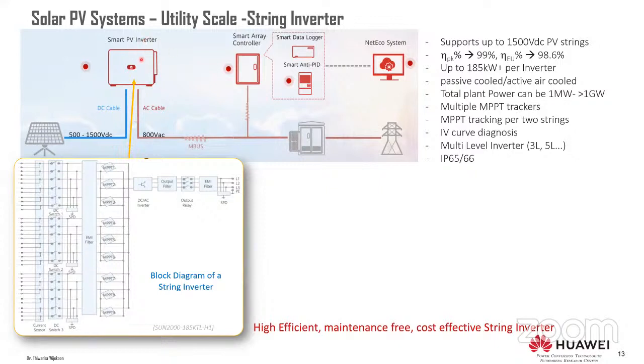The output of a typical inverter goes up to 800 volts AC, again very close to the AC limit, which is 1000 volts AC, and then you feed into the grid. Typical inverter efficiency goes up to 99% peak, and then there is the Euro weighted efficiency. This is what we normally use to benchmark. It includes 5%, 10%, and also 20, 30, 50, and so on, all the power range efficiencies accumulated. So this gives you an overall picture of how effective your inverter is in all scenarios.